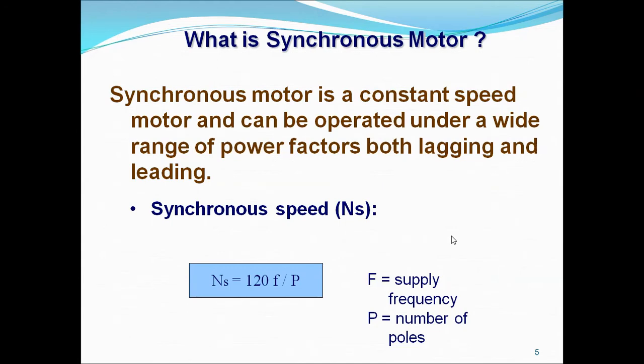So what is a synchronous motor? How does it differ from other motors? A synchronous motor is a constant speed motor and it can be operated at a wide range of power factor, that is both lagging and leading power factor. Some other motors will operate at only lagging or only leading. But in a synchronous motor, we have the advantage that it can be operated at both lagging and leading power factors. And it will run at synchronous speed.